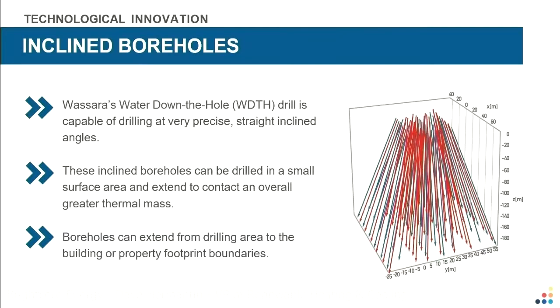And here's a computer graphic of that design. And you may notice that this graphic is a bunch of lines, and they're angled as they extend downward. So what this represents is the surface area inside of a building where this system was installed. It was about a 14,000 square foot open area in a basement, a parking garage, where they drill downward directly vertically and also at inclined angles. This allows to capture a lot more thermal mass than could be considered before with conventional drilling technologies.